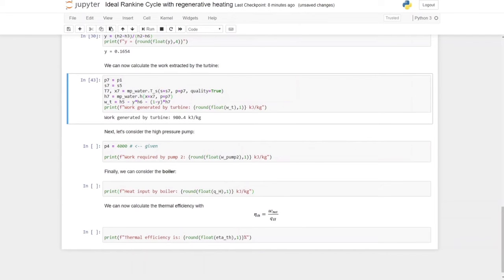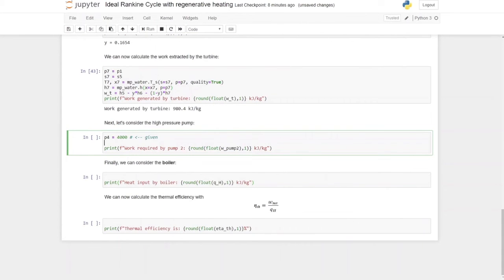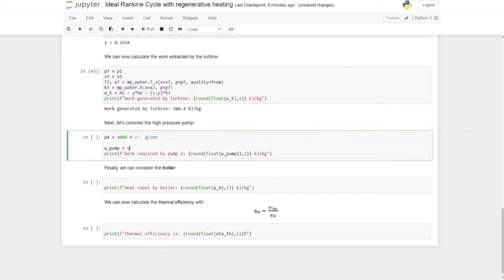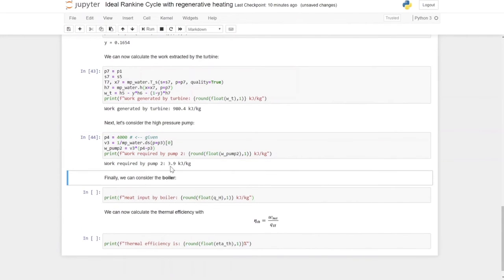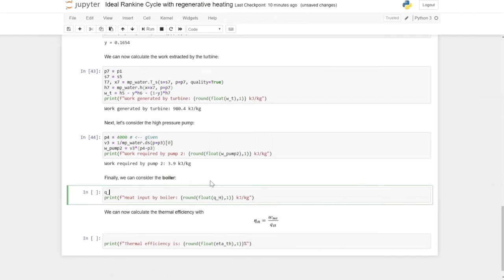Next, we consider the high pressure pump, which pumps feed water from the feed water heater through the boiler at 400 kPa up to 4000 kPa. The work of pump 2 equals specific volume V3 times (P4 minus P3). V3 is the inverse of density, calculated for saturated liquid at P3, taking the first element. Running this, the energy required by the high pressure pump is 3.9 kJ/kg.